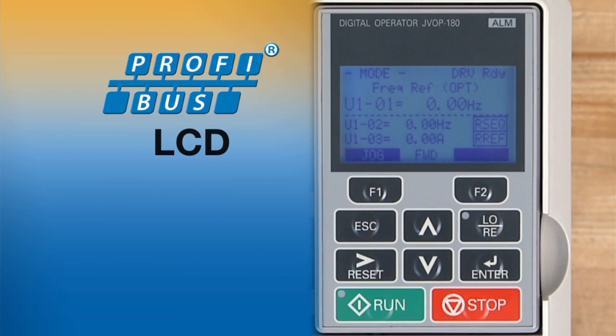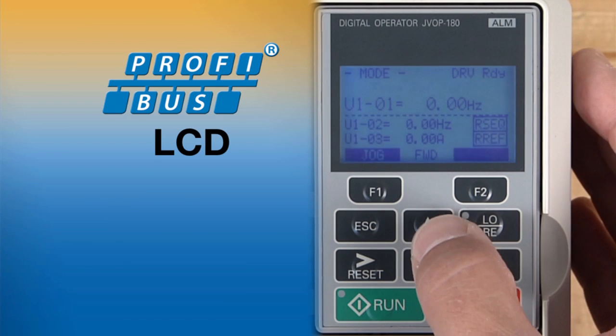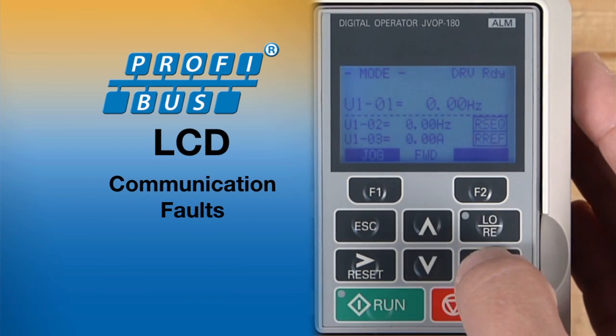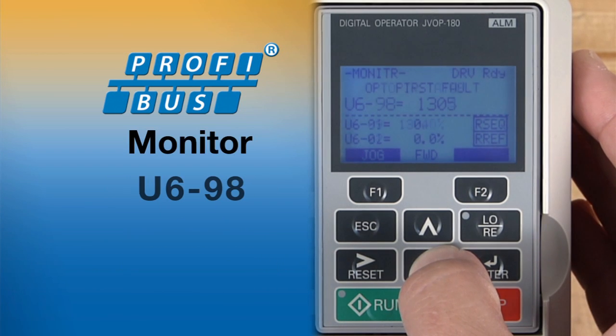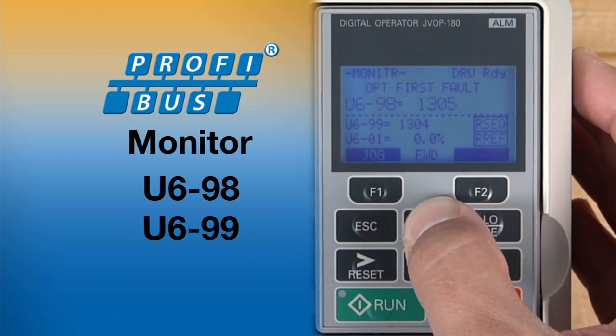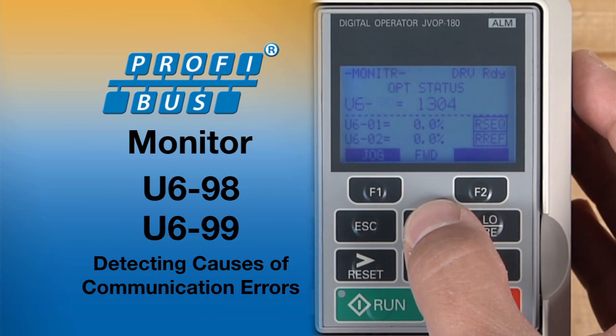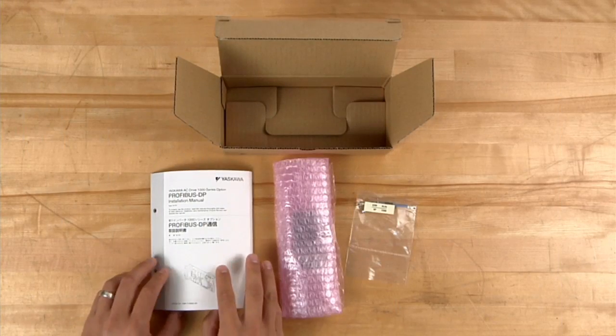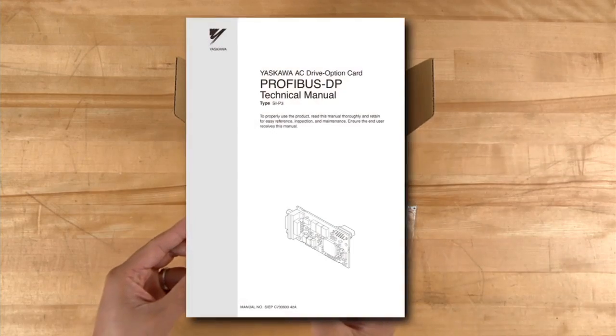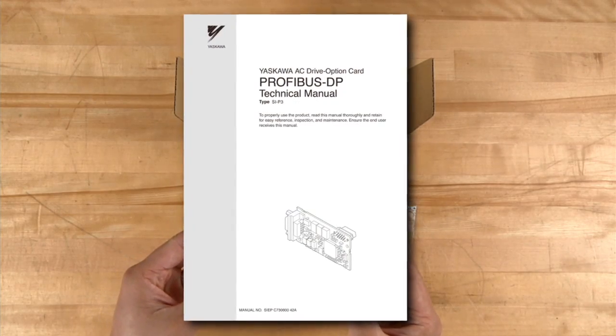In the same way, the LCD display of your Yaskawa drive can offer information on communication faults that can be valuable for troubleshooting. Monitors U698 and U699 are particularly useful in detecting the cause of communication errors. Further information on fault codes is contained in the SI-P3 technical manual.